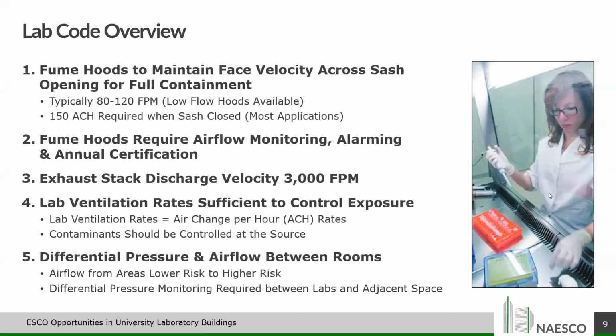Now this picture on the side here shows a lab user working inside a hood, and there's a sash opening here. And what we're talking about is making sure that the air velocity is flowing through that opening at a speed of generally 100 feet per minute is what the set point is, particularly at university. And the reason is that if you don't have good face velocity, there's a chance that anything someone's working on in the fume hood could come back out in the user space, and that would be a catastrophe. So it is super important that that face velocity is maintained at all times.